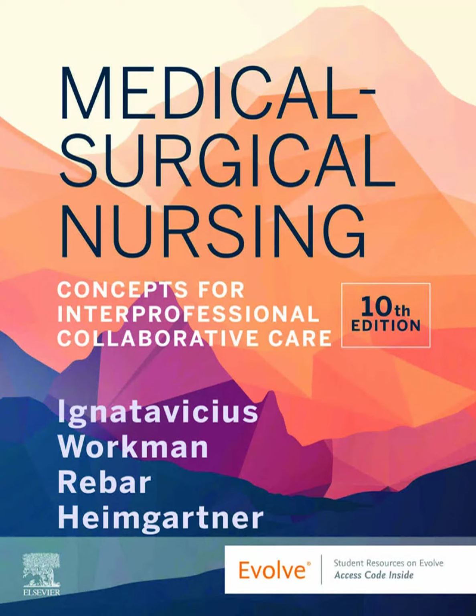And luckily, technology has given us some safety nets here in the form of smart pumps. Yes, smart pumps are a huge advance. They use integrated dosage calculation software and institution-specific drug libraries with DoseGuard technology. How does that help? They're designed to reduce adverse drug events, or ADEs, by flagging the nurse if the programmed dose or rate falls outside the preset safe limits defined by the hospital pharmacy for that specific medication. Sort of a double check. Exactly, a technological double check.